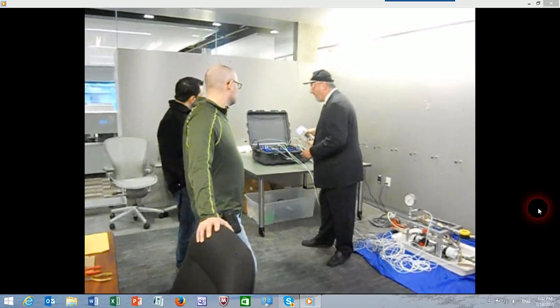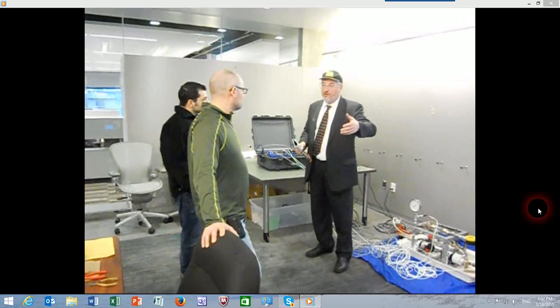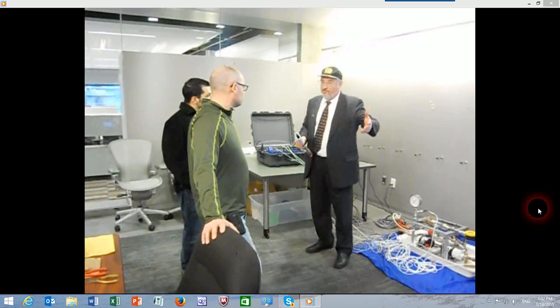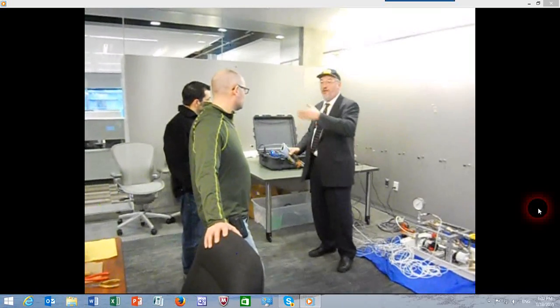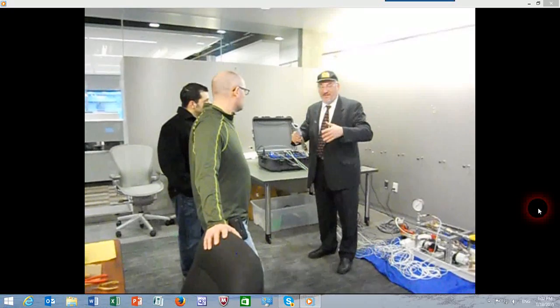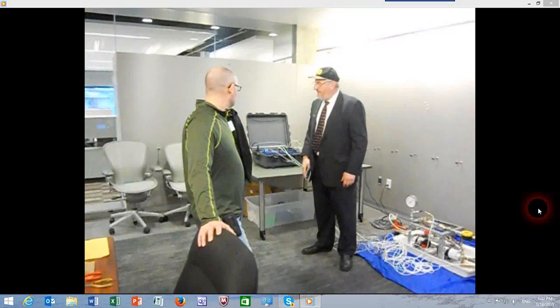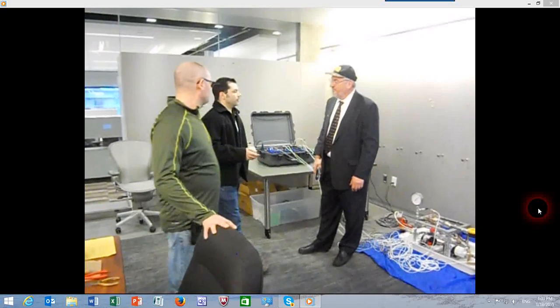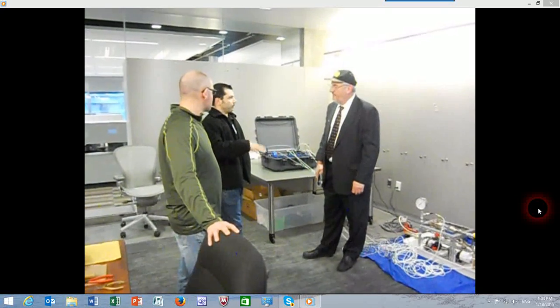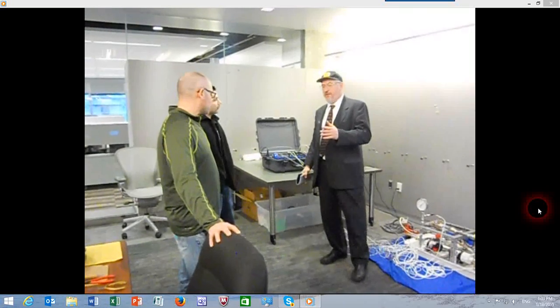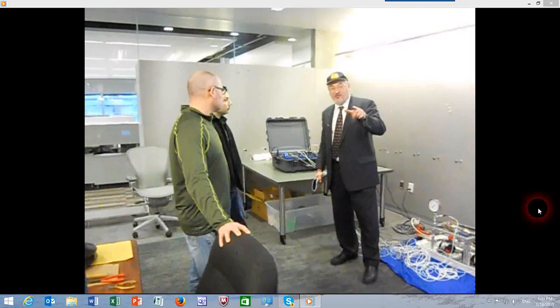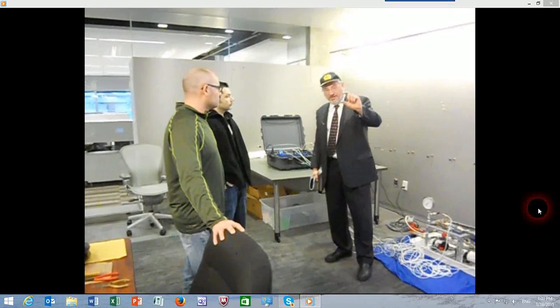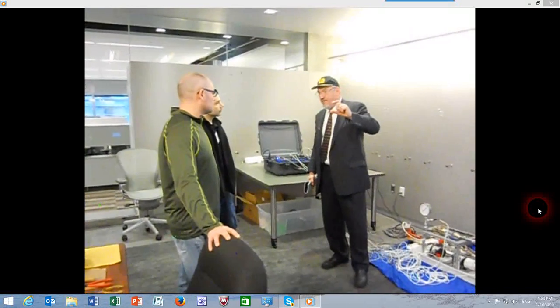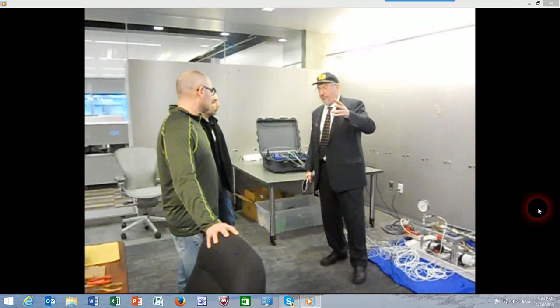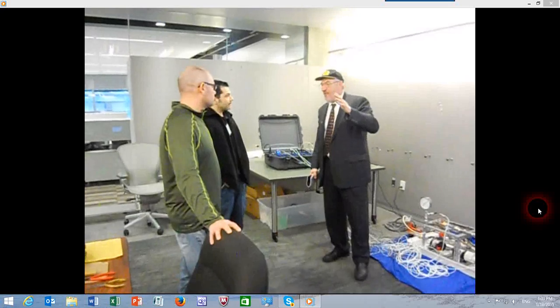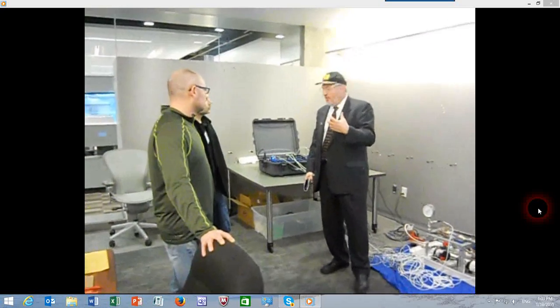So you can, for example, measure vibration on the motor inboard and a pump outboard, or you can do vibration on one pump, and a second channel could be on another pump, or compressor. You can mix and match data as long as you can label them. So in addition to just knowing what your temperature is, your pressure and flows, you know how you have to perform. Exactly. If your pump is supposed to be 75% efficiency, you measure it right now, it shows 68% efficiency. So that difference in 7% efficiency translates into dollars, and it'll tell you at this cost and this percent operation, that costs you $174,000 a year. Well, the next thing is, what do you do about it?